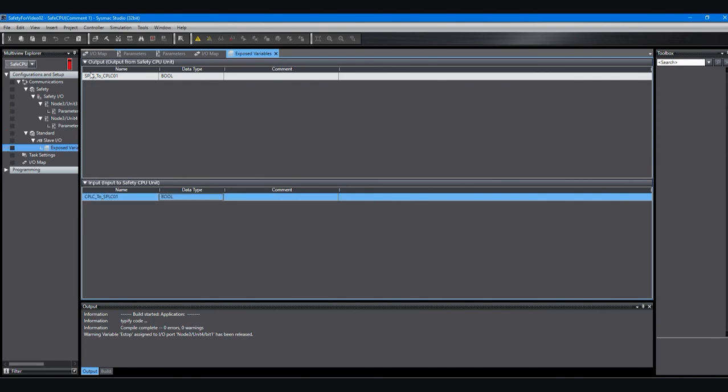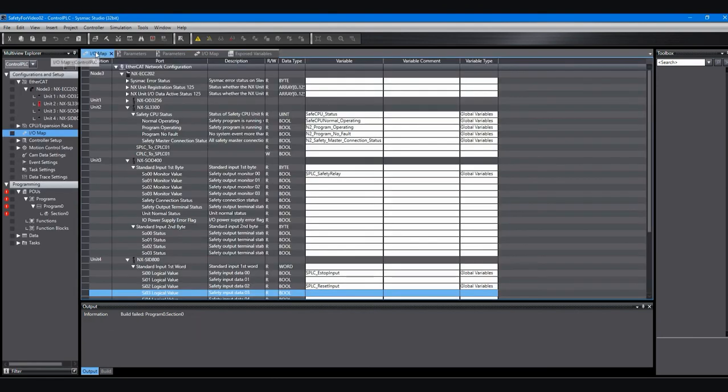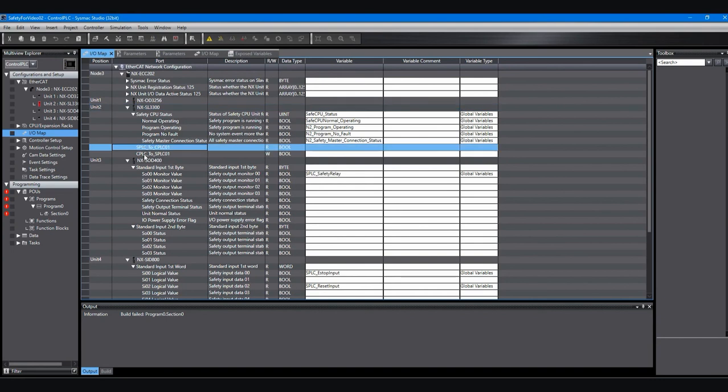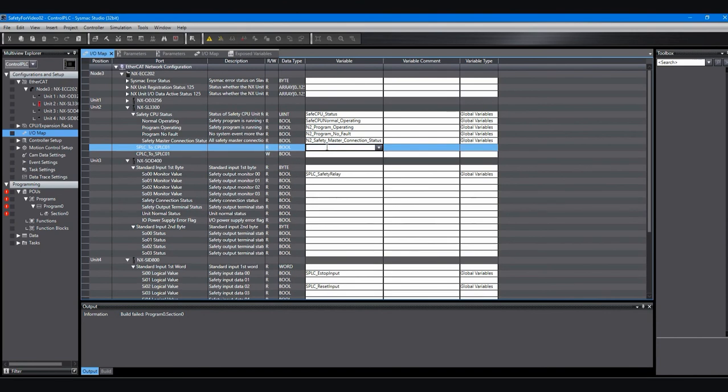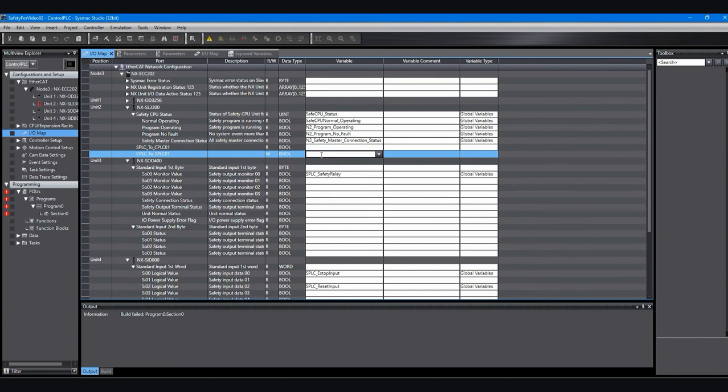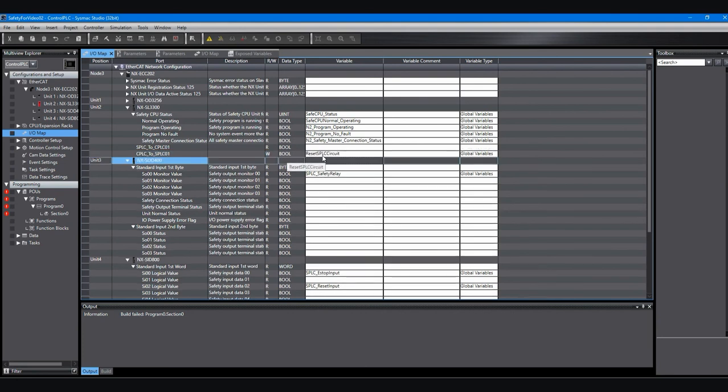But then once I get done creating those, if I go back to the IO map for the control PLC by clicking on that tab and then go up here and look at the IO table for the NX safety controller, the NX SL 3300 there, you can see those two new variables that I just created are added in. And if you look at this, I can create a variable for those there. And if you look at the attribute of those there, one is read only and one is write. So I can now add these variables to my program in the safety PLC and I'll be able to write to them from the control PLC. I can't use them as safety inputs on that PLC, but for standard input stuff like a simple reset or a selection of a zone maybe or something like that, I could use those standard inputs. And that will not take any special communications programming. It's just create the program in both controllers correctly.